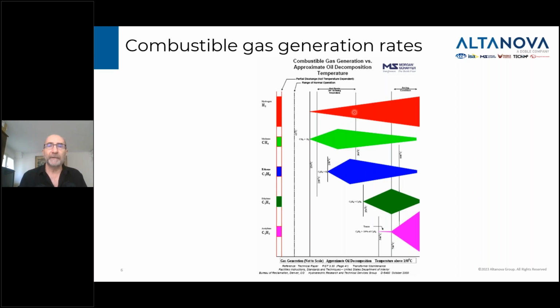So as the temperature changes and increases with the fault, you're generating more and more hydrogen, and the rate of generation accelerates. For methane, at 140 you start seeing a rate of generation of methane, and it will increase up to a certain temperature. If the temperature of the fault exceeds 240, 250, now you start seeing ethane. So as the ethane rate of generation increases, the rate of generation of methane diminishes. And it continues like that. The next one will be ethylene. As we reach the temperature to generate ethylene, the rate of generation of methane and ethane starts decreasing, and the rate of generation of ethylene increases.